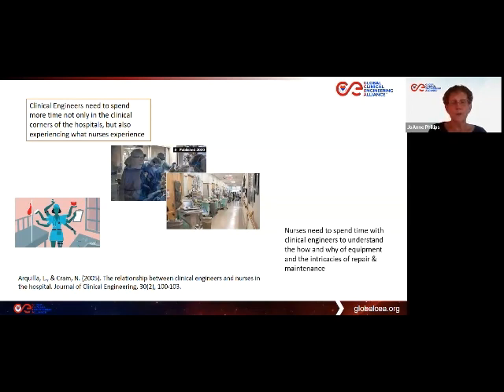And I think part of that will be so that you all don't get as many pieces of equipment like this. I don't know if you can appreciate this, but it's a yellow tag that says repair, but it doesn't say anything, or it says broken. So, help nurses to understand, if you write broken, what will happen is that that piece of equipment will go to engineering, will be evaluated, assessed, and sent back to you. Unless you tell the engineer what it is that you need to fix, they're not going to be able to fix it. The analogy is, you don't take your car to the dealer and say it's broken. You have to be able to describe exactly what's wrong.